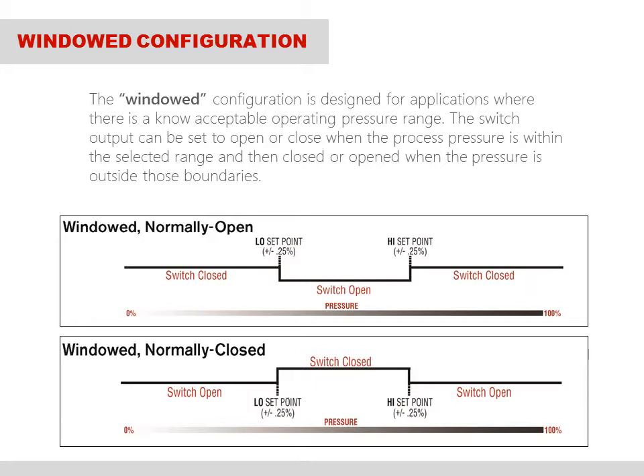This particular switch functionality makes the 815 well suited for wellhead pump control and shutdown, where the 4 to 20 milliamp signal can be the primary input to a pumping unit, and the switch output can serve as an emergency failsafe device. The upper diagram is just the opposite of the lower diagram.